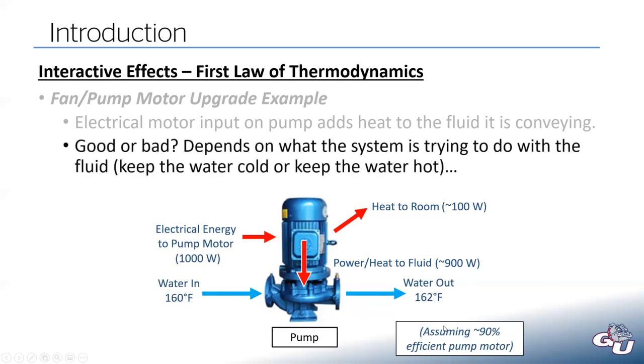So is this a good thing or a bad thing? And it really depends on what the system's trying to do with the water. If the system you're looking at is trying to keep the water cold because you need some chilled water in some process in your building, then this is a bad thing because we don't want the heat to go into the water and warm it up because we're trying to keep the water cold. But conversely, if we are moving hot water, like in this example, we're trying to keep the water hot, 160-ish degrees. Well, that heat into the fluid, that's not a bad thing. We're trying to keep the water warm anyway.